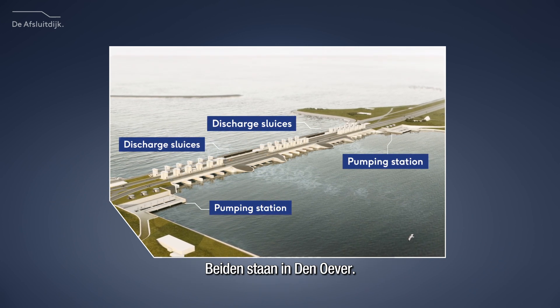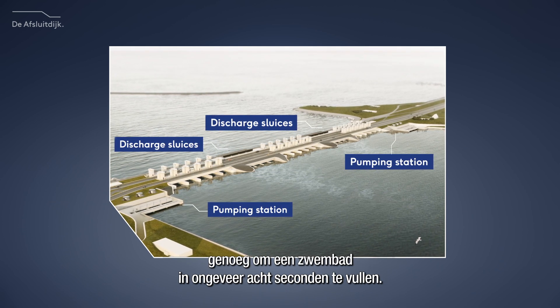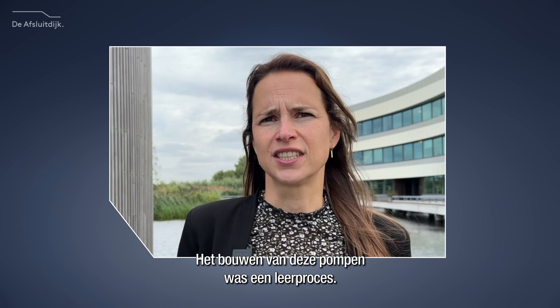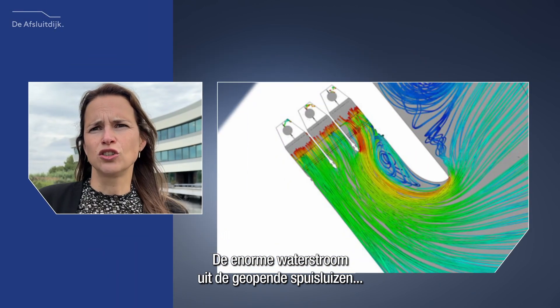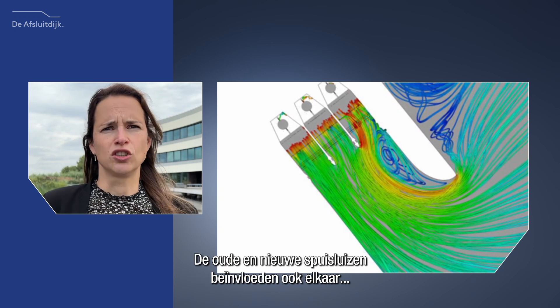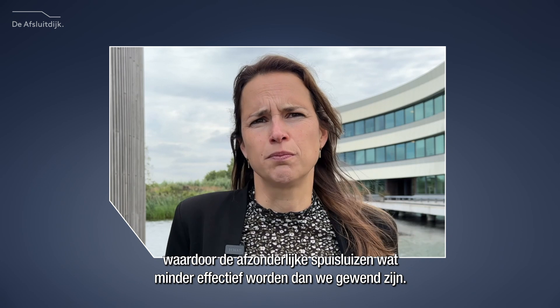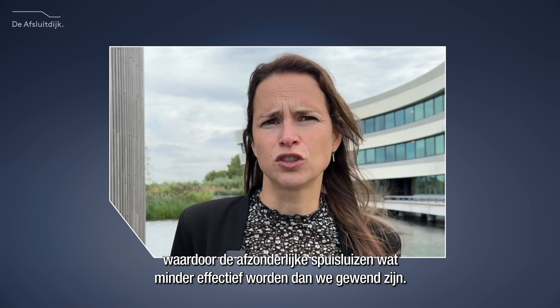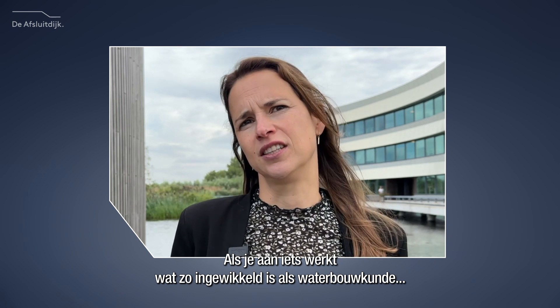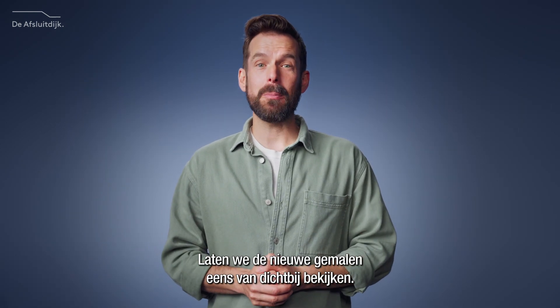Both are located in Den Oever. The pumps have a capacity of 300 cubic meters per second, which would fill a swimming pool in around 8 seconds. The building of these pumps was a learning process — the enormous flow of water from the open discharge sluices disrupts the water level and the inflow of the pumping stations. The old and the new discharge sluices also have an impact on each other. As a result, the individual discharge sluices become a little less effective than we're used to. When you're working on something as complicated as hydraulic engineering, even 1 plus 1 isn't always 2.